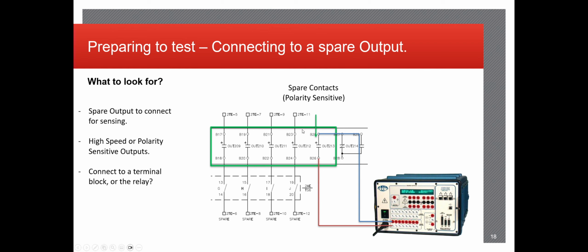Most of the times as well, these outputs may not even be wired to any terminal blocks or knife switches in the cabinet. So you'll just have to go to the back of the relay again and plug it in. But that's not too big of a deal because you plug it in once and you probably won't unplug it again until you're all done testing.